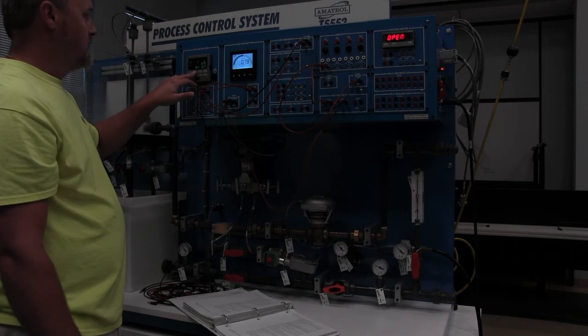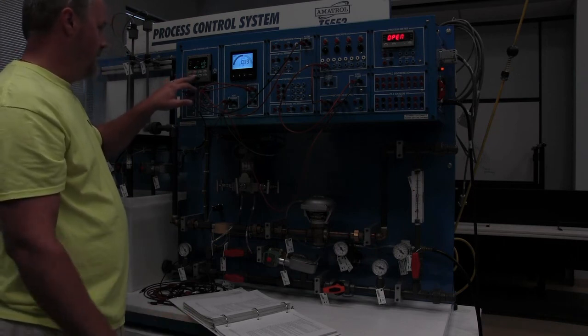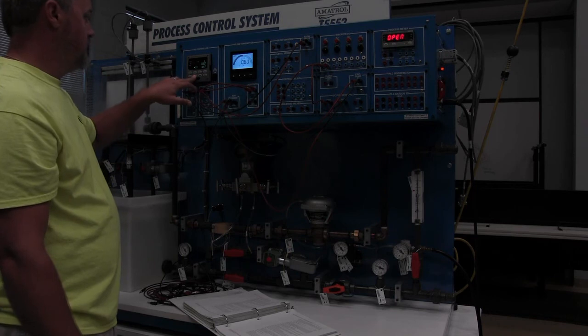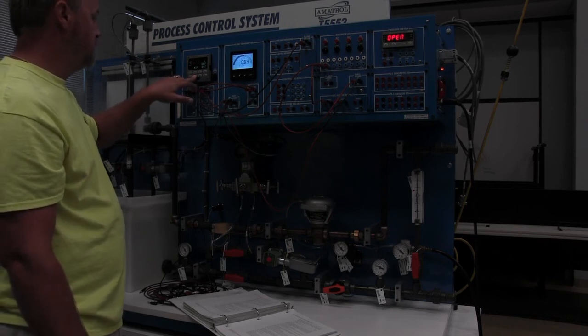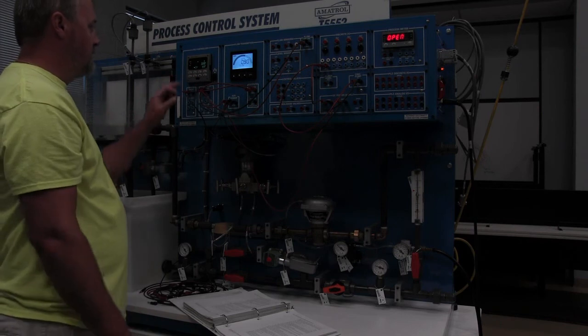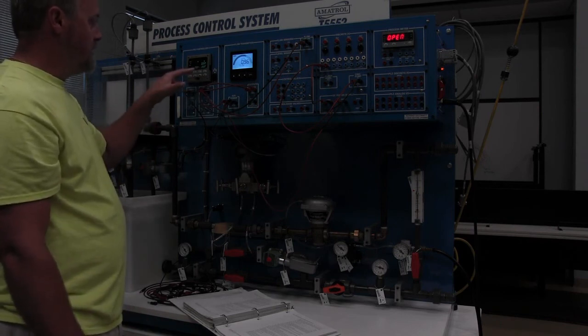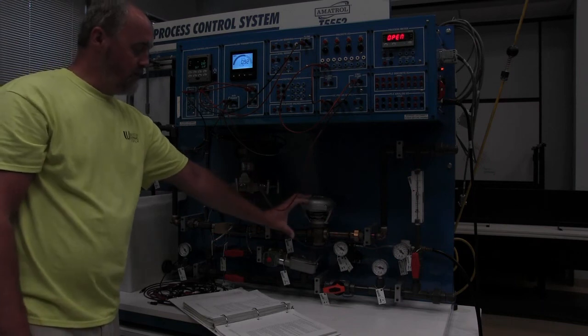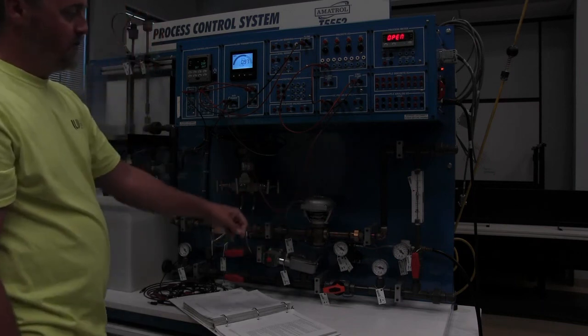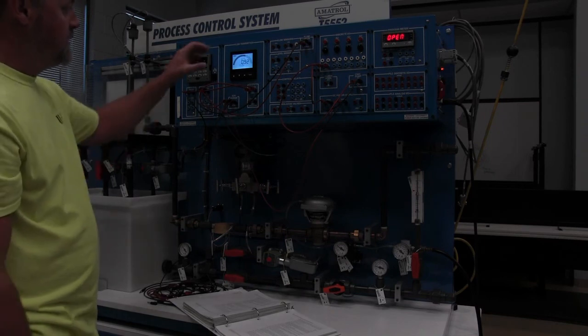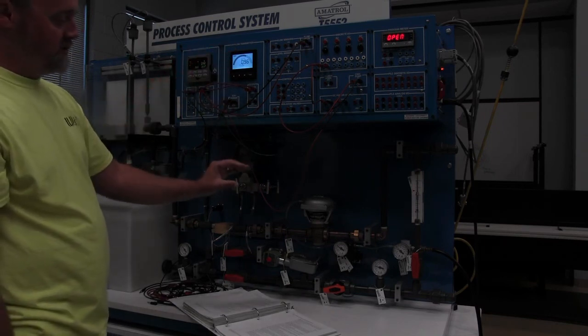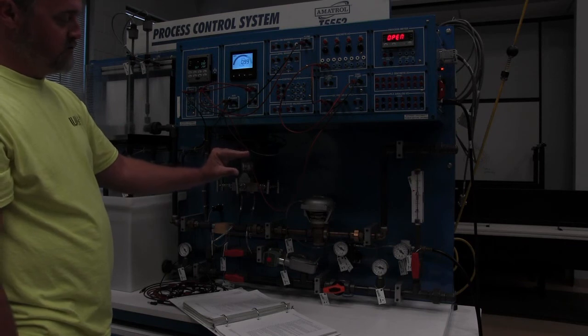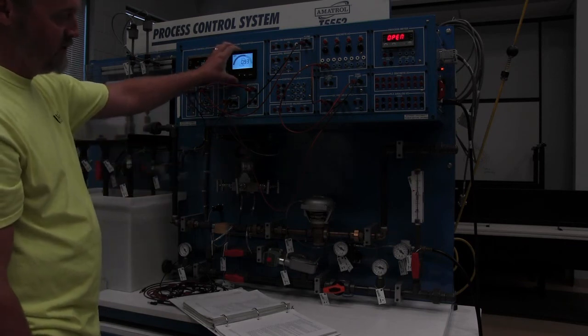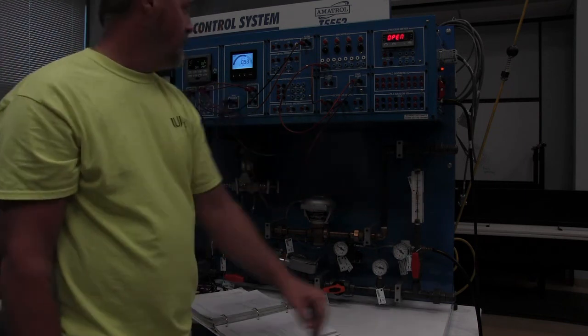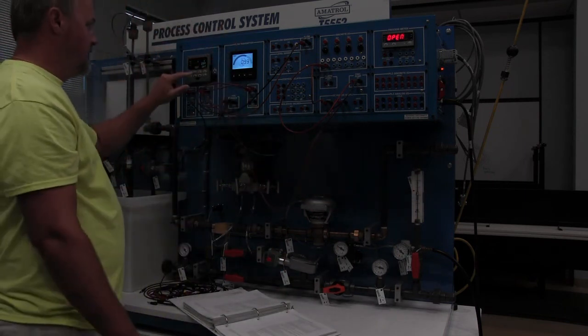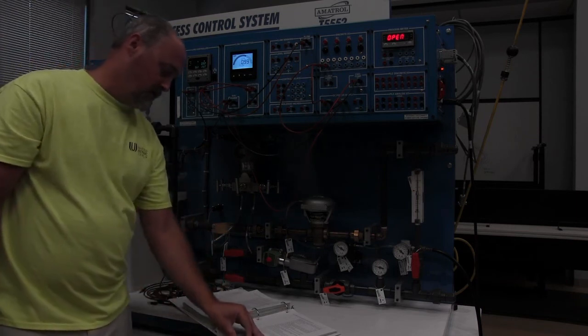If I was to change my set point to, I'm going to change my set point to a 1.0. As I do, the output will increase, which will open this air valve a little bit more to allow 1 gallon per minute to go through. Once it gets to 1 gallon a minute, it's going to open and close that valve just to maintain that 1 gallon a minute that's going through. Rotary meter is reading about 1 gallon a minute, so is the flow transmitter. We're outputting, everything's working like it should.